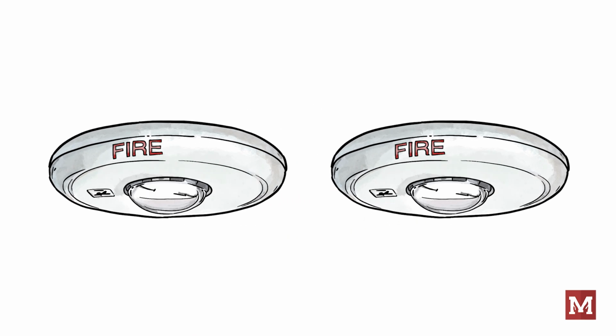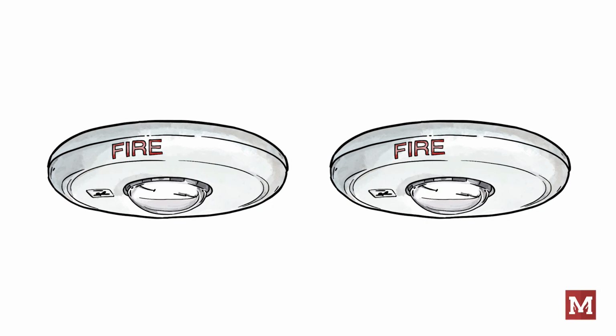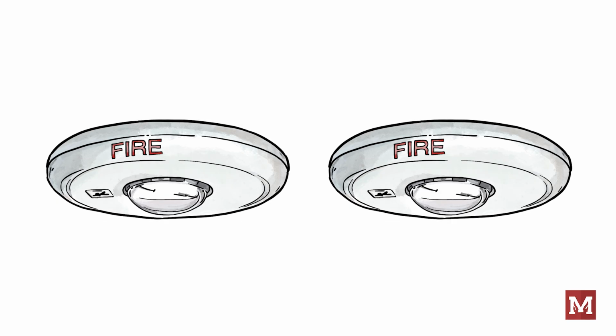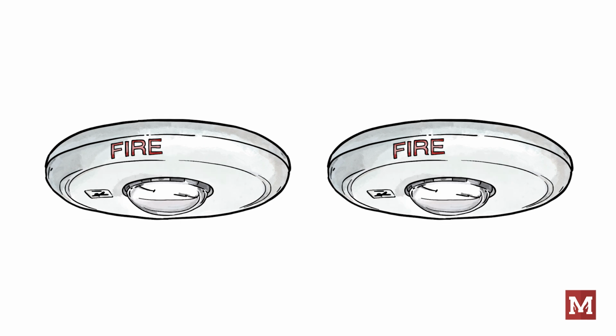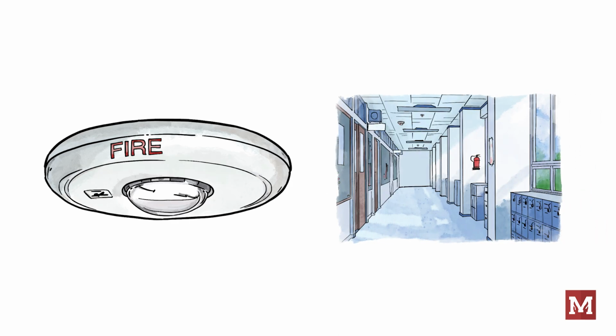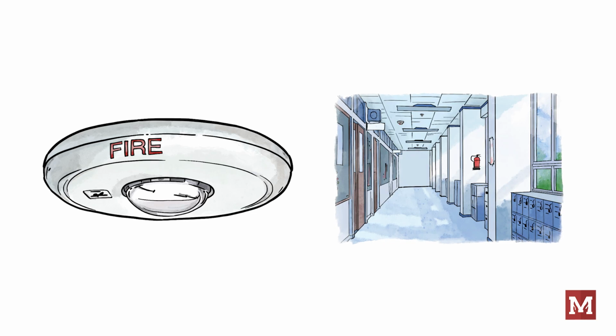People with epilepsy can have seizures or other significant adverse effects by significant flashing alone, but certainly that risk goes much higher if multiple flashes occur and they're offset from each other, coming from multiple directions. So if we can see 2 strobes within our field of view in one shot, what we can see, they need to be synchronized and flashing at the same time. Historically, fire alarm systems were not coming out of the box synchronized, and we often had to have an additional component added in order to synchronize a circuit.